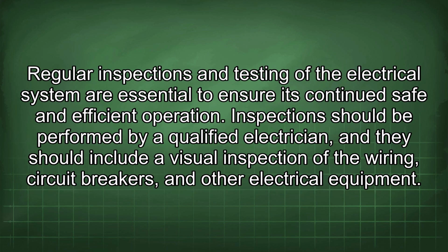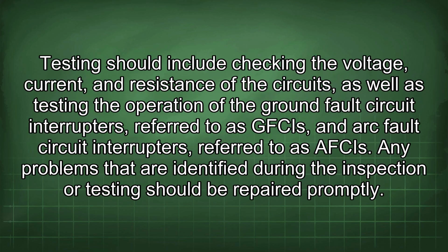Regular inspections and testing of the electrical system are essential to ensure its continued safe and efficient operation. Inspections should be performed by a qualified electrician, and they should include a visual inspection of the wiring, circuit breakers, and other electrical equipment. Testing should include checking the voltage, current, and resistance of the circuits, as well as testing the operation of the ground fault circuit interrupters, referred to as GFCIs, and arc fault circuit interrupters, referred to as AFCIs. Any problems that are identified during the inspection or testing should be repaired promptly.